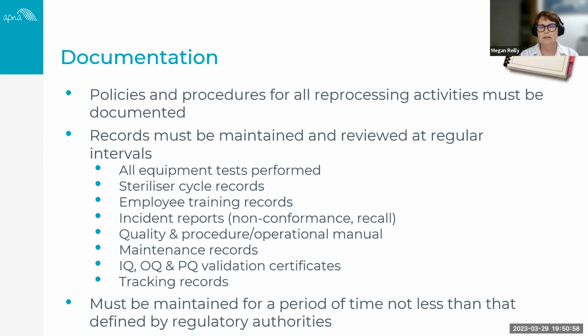So all of your equipment tests that are performed, your sterilizer cycle records, any equipment cycle records, your employee training records, incident reports, so if there's been a non-conformance such as a sterilisation failure, your recall reports, any quality and your procedure operational manuals, and that includes the equipment manuals as well, any maintenance records, your validation certificates for IQ, OQ and PQ, and of course your tracking records. So these need to be maintained for a minimum period of time, and you need to look at not only your practice policy for retaining records, but also what is defined in the regulatory authorities, and they do differ from state to state.